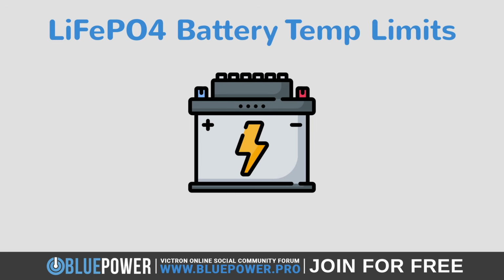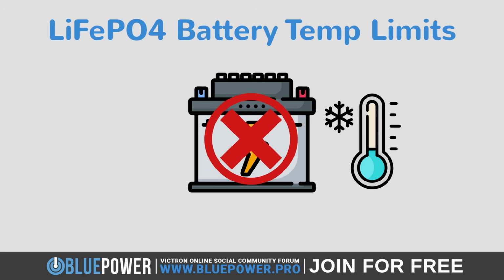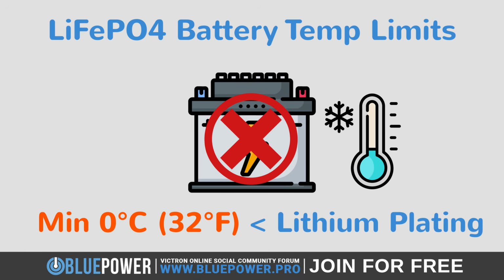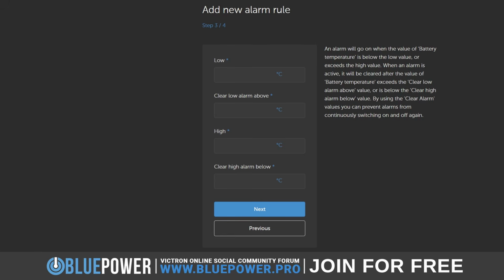It is very important to note that lithium iron phosphate batteries do not like cold weather, especially when charging. When a lithium phosphate battery is charged below 0 degrees Celsius, a chemical reaction called lithium plating occurs. This reaction forces lithium ions to move too quickly, accumulating on the anode's surface. The result is a battery with a higher internal resistance, permanently decreasing the battery's capacity. With that said, setting the low value anywhere above 5 degrees Celsius is a safer bet. I'm not in a cold climate, with my battery only reaching lows of around 19 degrees Celsius, so I will keep this value at 15.